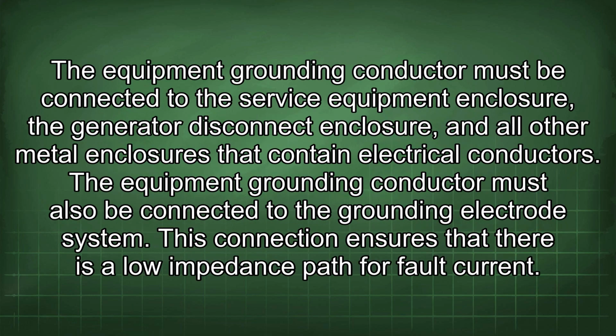The equipment grounding conductor must be connected to the service equipment enclosure, the generator disconnect enclosure, and all other metal enclosures that contain electrical conductors. The equipment grounding conductor must also be connected to the grounding electrode system. This connection ensures that there is a low impedance path for fault current.